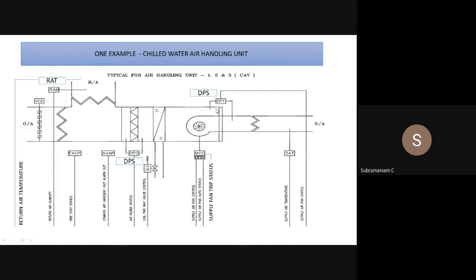For example, if I want to know whether the fan is running or not, I have to put a differential pressure switch and take it as a binary input to my controller. If I want to measure the temperature, I have to put a temperature sensor and connect it to the BMS. That will tell me the temperature value. If I have the fan, there will be a starter panel, whether DOL starter, soft starter, or star delta starter. I have to do wiring to that hand-off-auto switch and make it work automatically. So how the wiring has to be done with the relays, NO and NC contacts: we have to take the wiring diagram and do all that.